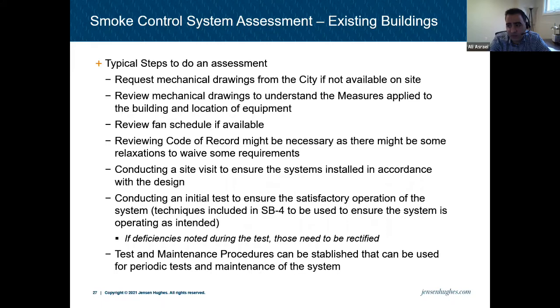If you're lucky, there's a fan schedule there. You can review the fan schedule. The same steps, we have to go back, and the only challenging thing here is that we have to understand what the code of record was at the time, because we can't compare the design of 30 years ago with the new code requirement and say this is all wrong, you have to redo things. Like, no, the system was installed back then. We have to see what the requirement was back then and compare it with that requirement and see, okay, back then they asked for a 5,000 CFM fan, or they didn't even ask for a fan in this area. So they're good.